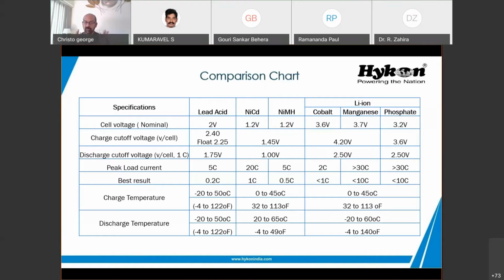If you look at lead acid, it is a 2 volt cell. But nickel cadmium has only 1.2 volt. So if you want 12 volt, you need 6 cells of lead acid battery. You need a larger number of cells in nickel cadmium. Like that, in cobalt it's 3.6 volt, manganese is 3.7, and LFP is 3.2. That is, different chemistries have different voltages. So you have to take care of that when you design a battery.